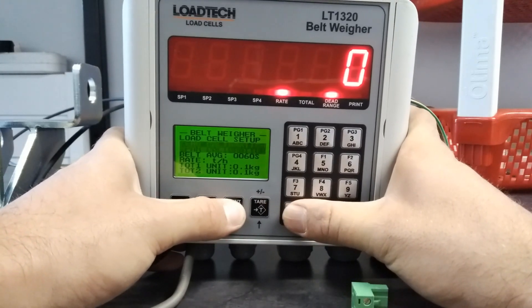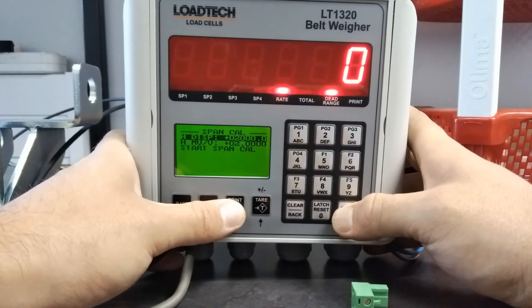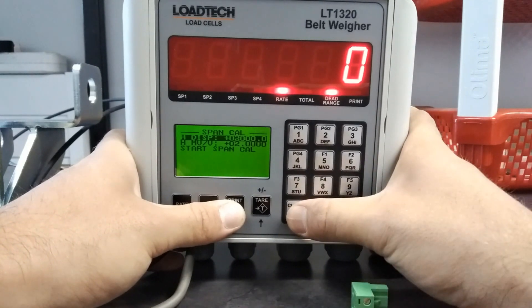Next go to span calibration. Set your high display, which is going to be the combined weight of your load cells. Set your high millivolt per volt. If you don't have the high or low millivolt per volt, that's fine. You can select start zero calibration or start span calibration and it will set it for you.